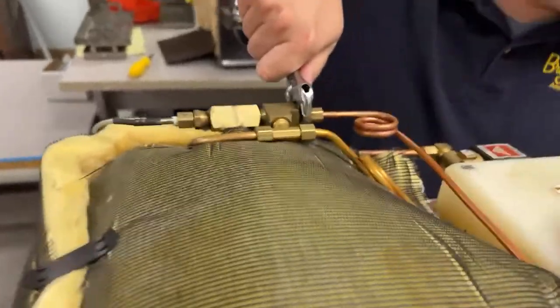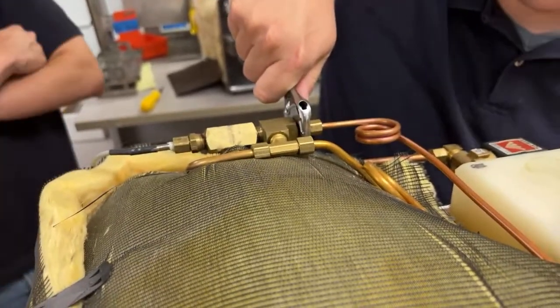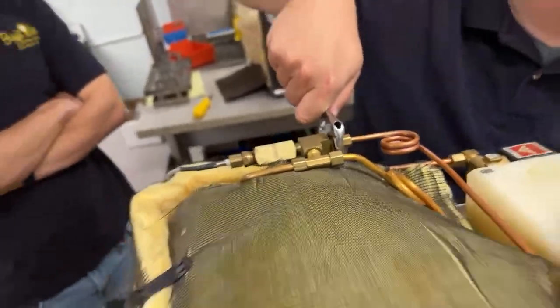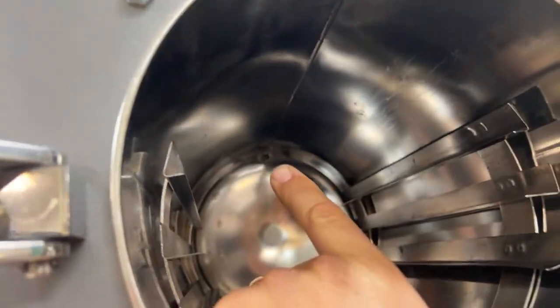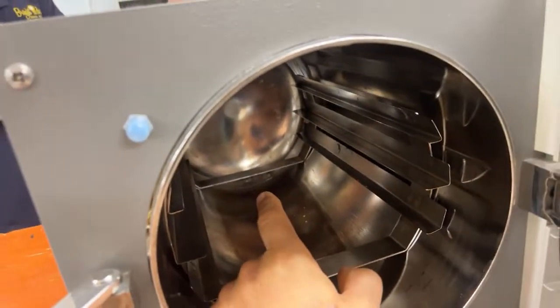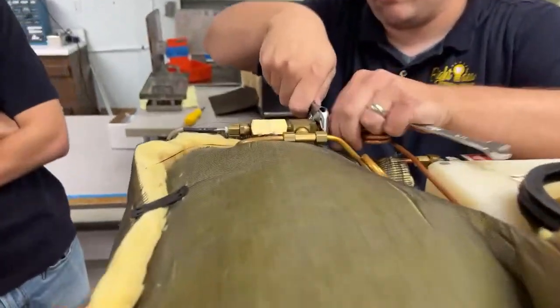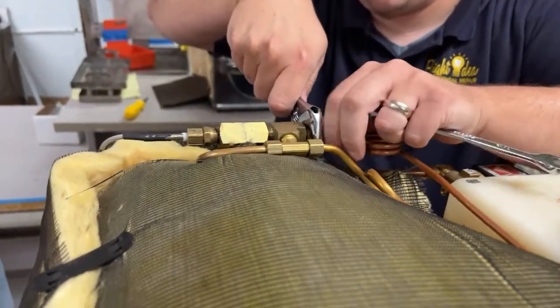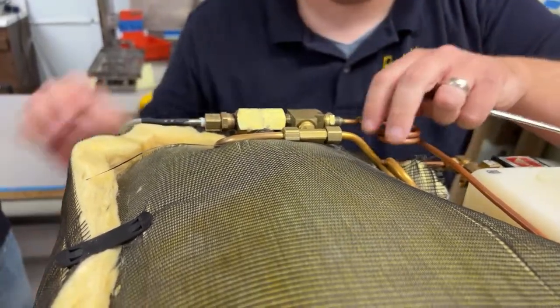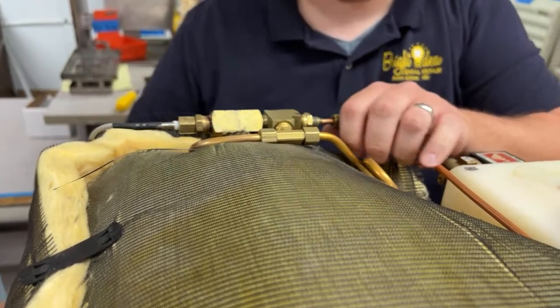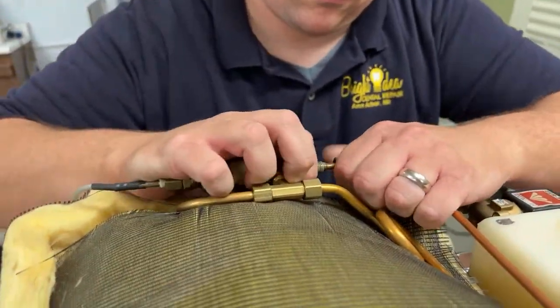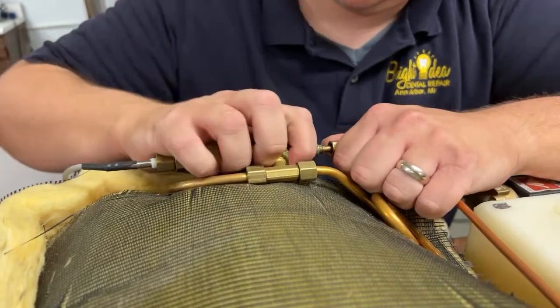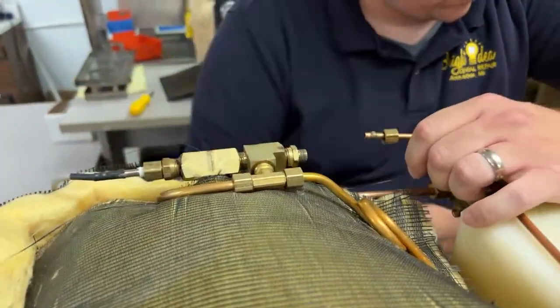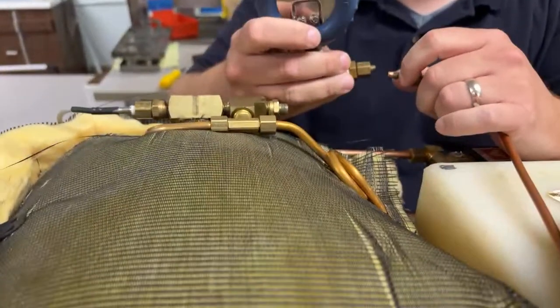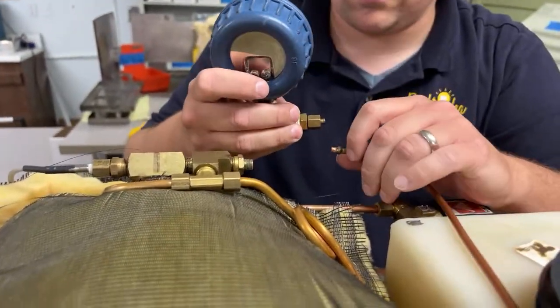That's being done. Put my men to work here. As I said earlier, you can see where the access is right there, and down at the bottom there's also a drain. What Kyle's doing is using a backing wrench to hold the manifold as he spins off the coiled tubing, and that's just going to release. Just jiggle the pipe a little bit and it'll come right out. That's going to be a little backwards. There you go.